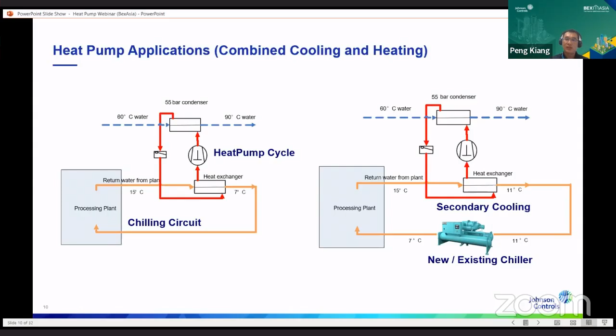Of course, there are many ways of applying this heat pump, depending on how high the hot water temperatures you need in your process are, and whether you need this cooling water for any other applications. Here is one actual example where we could tap into free cooling of the air through an AHU, for example, and you produce chilled water to pre-cool this AHU, from which you can scale up to bigger heating capacities on the other side, whether it's for pasteurization, clean in place, product heating, oil heating, syrup heating, all kinds of heating on the other end, which could be done by this heat pump.